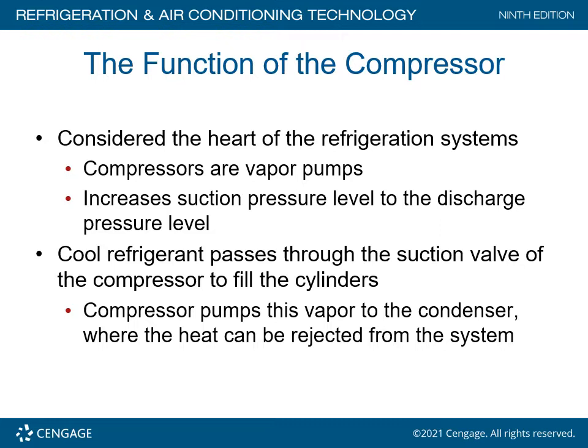The compressor increases the suction pressure level to the discharge pressure level. It draws refrigerant vapor through the suction valve to fill the cylinders, then pumps this vapor into the condenser where heat can be rejected from the system. Remember, the heat was absorbed in the evaporator.